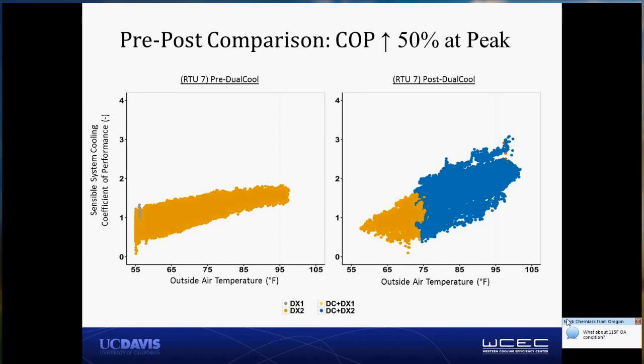This actually shows the same as the last one, so I'll skip by it. But what we managed to do was run for a period of time where we removed the dual cool equipment and, because all of our instrumentation was in place, measured the performance of the baseline vapor compression system. This shows RTU7, that one unit that runs consistently in DX2 regardless of anything. I wonder if it's not, frankly, just jumpered to run in DX2 24/7. And when we do this, we can measure directly the impact of the dual cool, and again we see that significant increase to coefficient of performance.